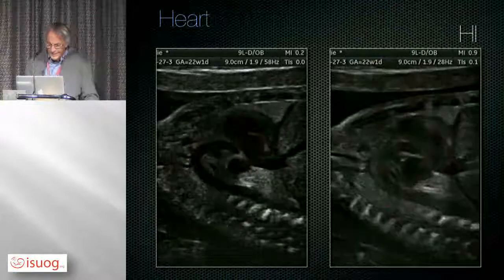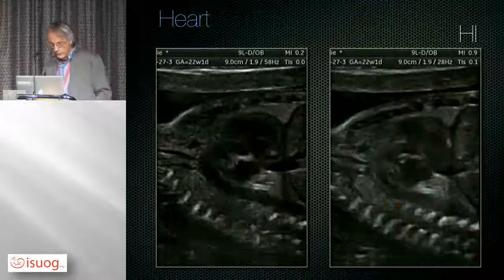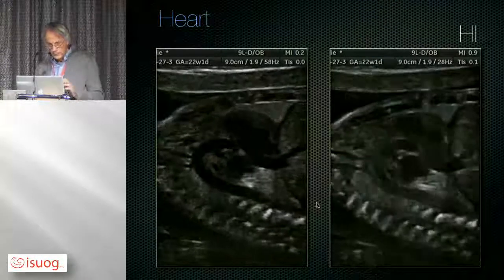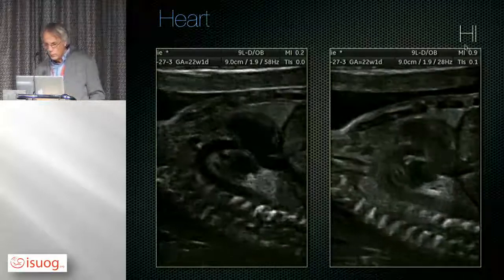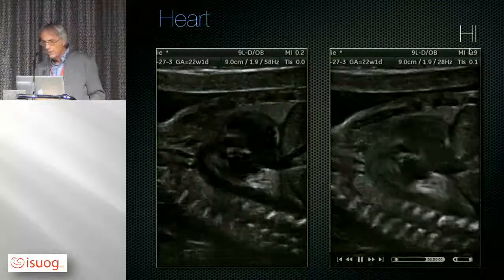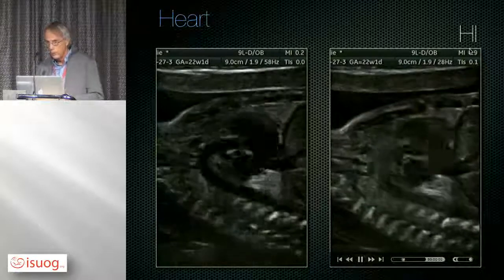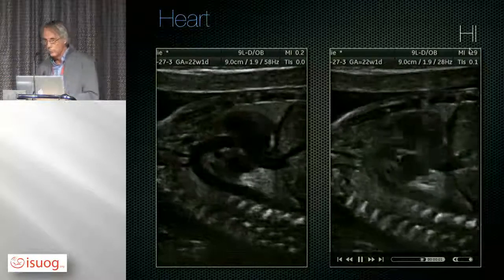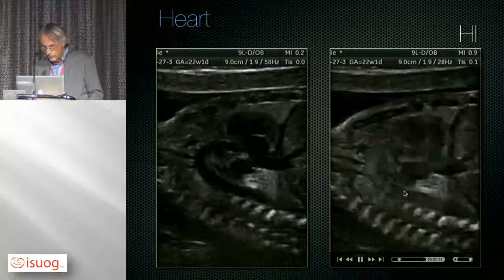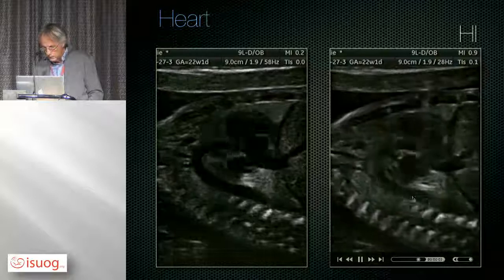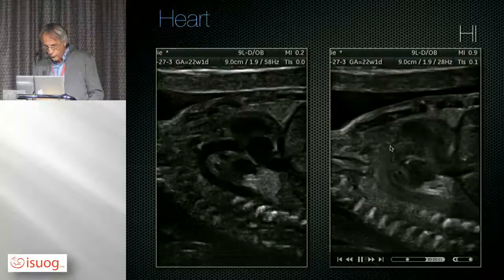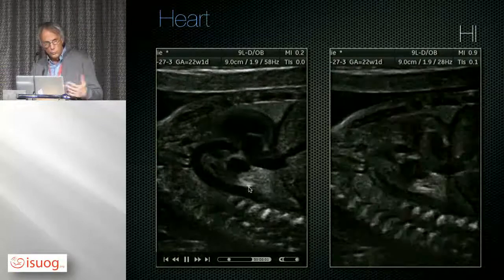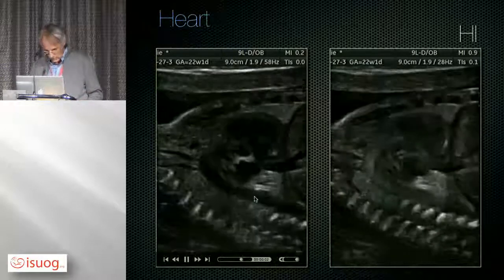Now, the heart, it's a little bit more difficult to use it because this was made with the same probe, but one is with the harmonic imaging. And if we want to improve the quality, we have to use the harmonic imaging. But it's difficult to use with this kind of probe on the heart because you have a kind of B-flow. You can see here, kind of B-flow. So for the heart, when I use it, I have to remove the harmonic imaging.